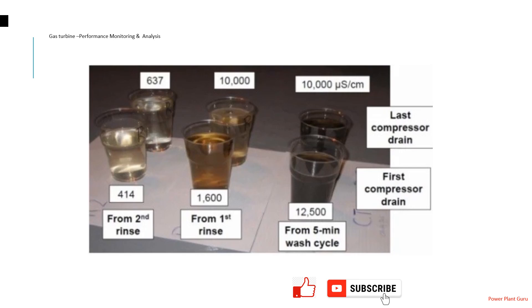You can see that the rightmost sample shows the initial water wash drain, and then how the water coming out from subsequent rinses gets cleaner and cleaner. This gives you an idea of how much dirt was present and how the compressor is now clean. You can also send the water samples to a lab to check conductivity. Feel free to ask any questions related to water washing in the comment section and we will try to reply.